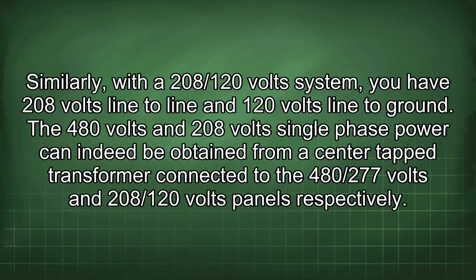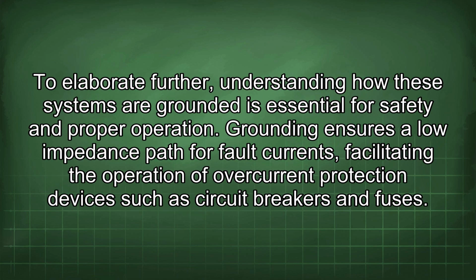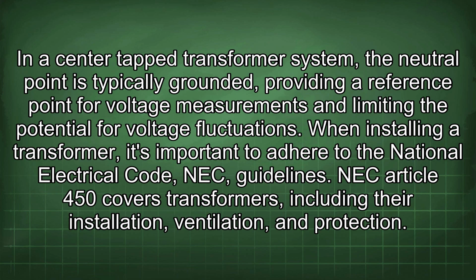The 480 volts and 208 volts single-phase power can indeed be obtained from a center-tap transformer connected to the 480/277 volts and 208/120 volts panels respectively. To elaborate further, understanding how these systems are grounded is essential for safety and proper operation. Grounding ensures a low impedance path for fault currents, facilitating the operation of overcurrent protection devices such as circuit breakers and fuses. In a center-tap transformer system, the neutral point is typically grounded, providing a reference point for voltage measurements and limiting the potential for voltage fluctuations.